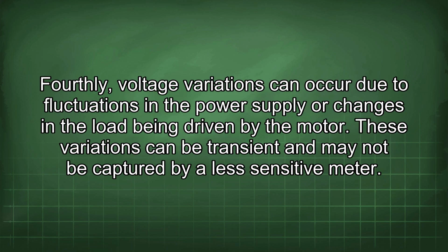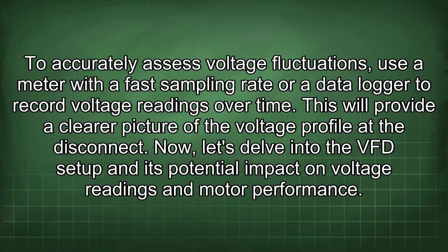Fourthly, voltage variations can occur due to fluctuations in the power supply or changes in the load being driven by the motor. These variations can be transient and may not be captured by a less sensitive meter. To accurately assess voltage fluctuations, use a meter with a fast sampling rate or a data logger to record voltage readings over time. This will provide a clearer picture of the voltage profile at the disconnect. Now let's delve into the VFD setup and its potential impact on voltage readings and motor performance.